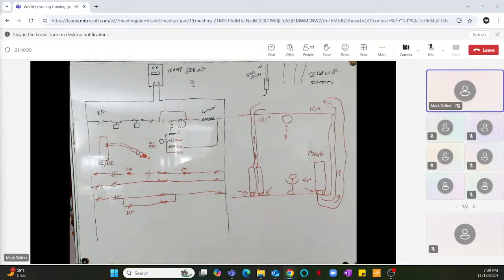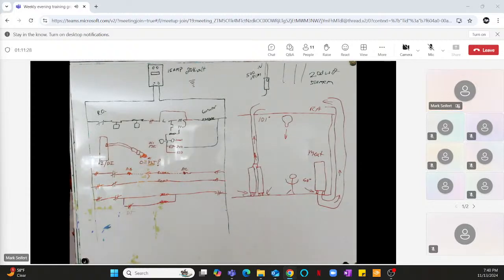So it's designed in software in the program. Emerson one is the easiest and works seemingly the best to me, as far as I'm concerned. The Danfoss one is weird because you have to add all this other stuff. Why can't they just say it's got it? I mean, it has that, but I guess it doesn't work right. I've never tried it. We've just always added all those other tasks, the miscellaneous tasks, and added it in there. But all it's doing, let's just say the RO calls for the compressor, turns it on. That's not there anymore. So it goes through the regular safeties. That could open at any time. And the contactor pulls in. This here is their oil pressure or not. Oil PSI with a question mark. If there is oil pressure, the controller will keep the RO closed.